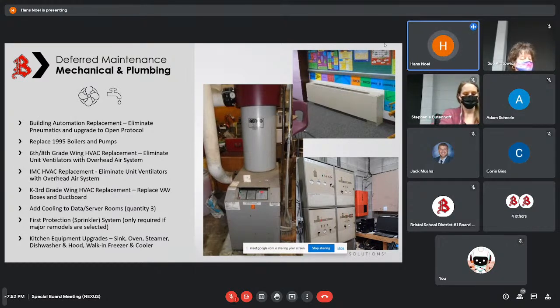IMC, this area — again there are unit ventilators, though you can't see them here because they're above the ceiling out in the hallway, providing air. I think there are 5 or 6 of them, I'd have to check the plans exactly. Again, we look to get rid of those and go to a single overhead air handling system, which saves money, reduces the amount of equipment needing maintenance, and upgrades the entire system.